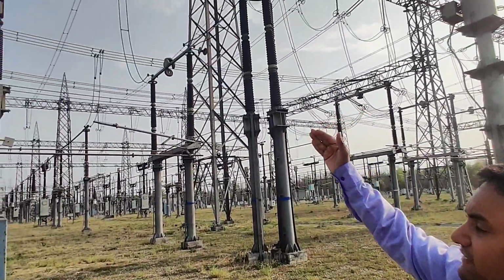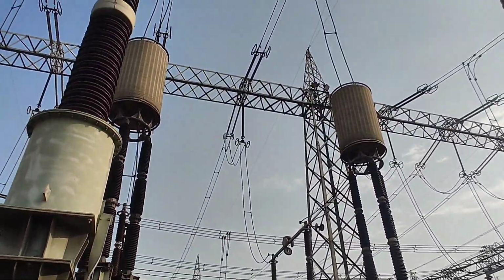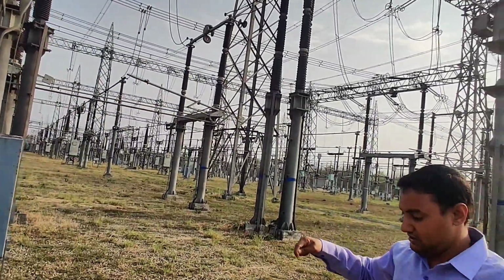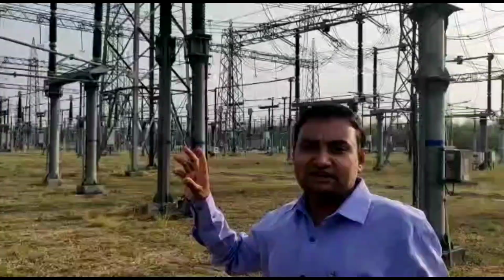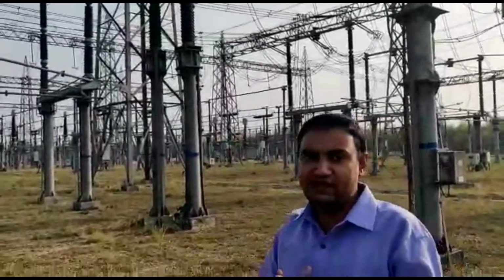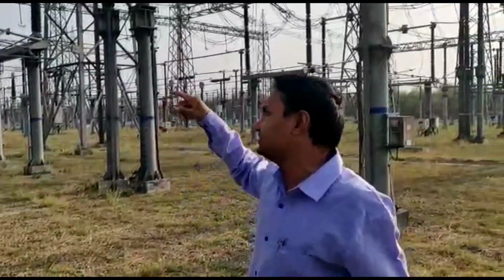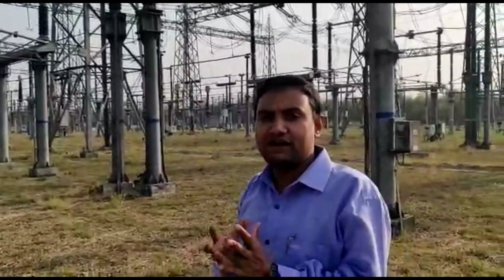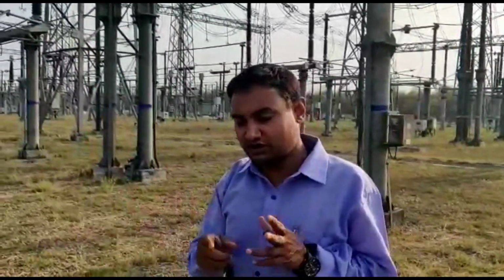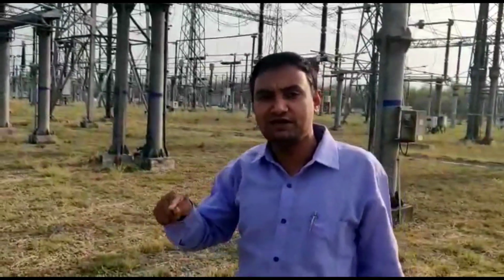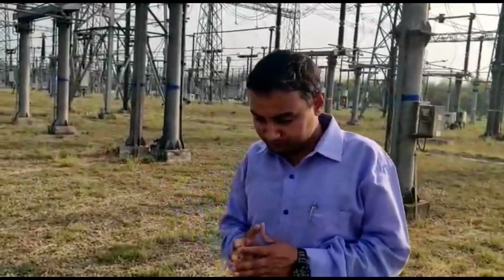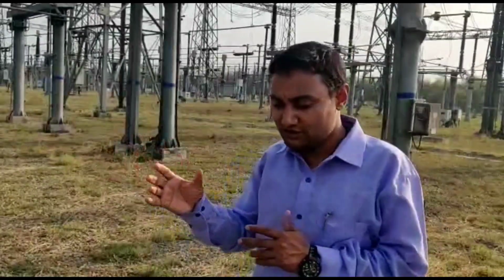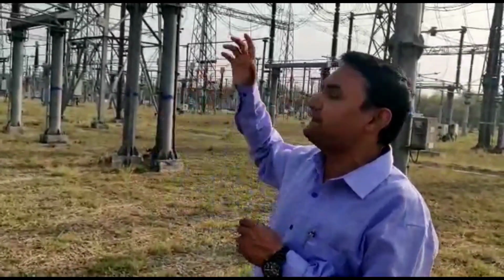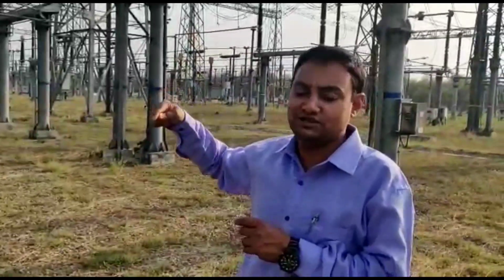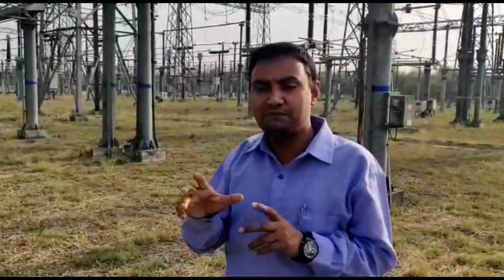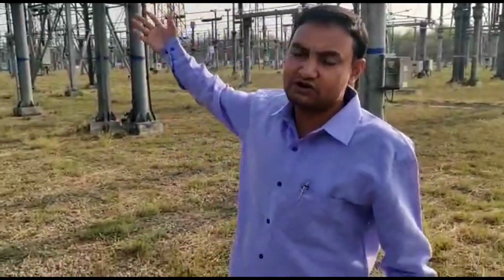If you see, after the wave trap, the line enters into the substation. So if there are any high frequency signals left after this CVT, those high frequency signals are trapped by using this wave trap. Inside this wave trap, generally it is a choke coil, and as you know, a choke coil is simply an inductance, and its impedance will be XL equals 2 pi FL. So the higher the frequency, the higher will be the impedance, and those high frequency signals will be trapped inside this wave trap, and it will provide a lower impedance path only for low frequency signals, and only low frequency signals will be transferred to the switch yard.